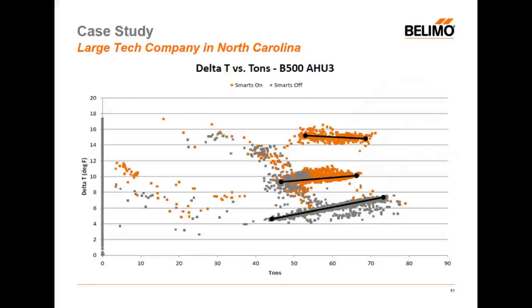60 tons of air handling, 60 tons of cooling, in this building, and we're going to run the smart valve in three modes. We're not going to enable the flow limiter or the delta T management. We're going to just operate it in position control. So we're listening to the thermostat, whether that's in the duct or in the room space. And when we do that, we call that position control.